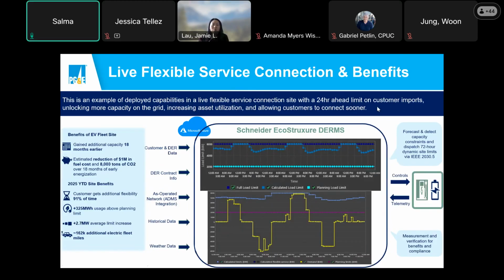On the right-hand side are screenshots from a live DERMS system for a Flex Connect customer—this is a battery operating on the wholesale distribution tariff. In the graph at top, in different shades of blue, is the 72-hour flexibility schedule sent by DERMS to the battery, as well as site and planning limits. Starting from the light blue line at the bottom, that's the planning load limit, the site limit before Flex Connect. The blue line at the very top is the full load limit enabled by DERMS via Flex Connect. The calculated load limit curve is the schedule DERMS sends to the customer, comprised of the dynamic site limits the battery must follow as sent by DERMS.